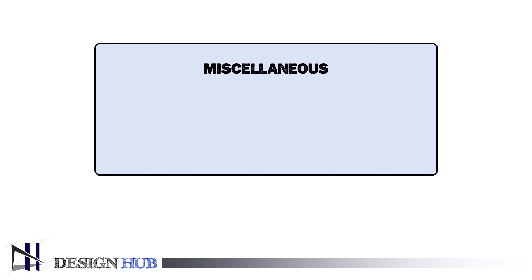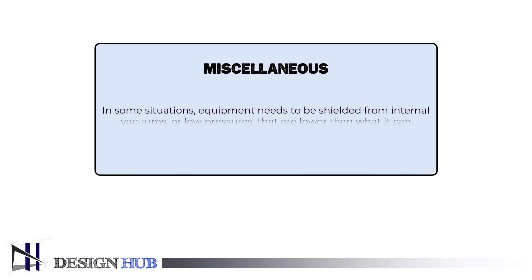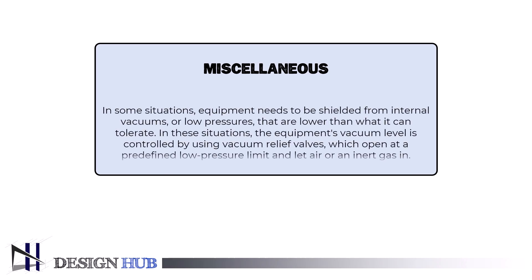Now let's see one miscellaneous condition that arises in the safety relief valve. In some situations, equipment needs to be shielded from internal vacuums, or low pressures that are lower than what it can tolerate. In these situations, the equipment's vacuum level is controlled by using vacuum relief valves, which open at a predefined low-pressure limit and let air or an inert gas in.